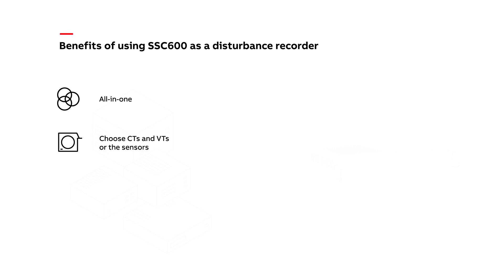Benefits of using an SSC 600-based system: Some of the benefits of SSC 600 as a disturbance recorder include space savings—it's all in one. There is no need to have a freestanding panel. You can choose either to have conventional CTs and VTs or go with the sensors. You have only one configuration software tool for all the protection relays from the Relion product family and also for SSC 600.